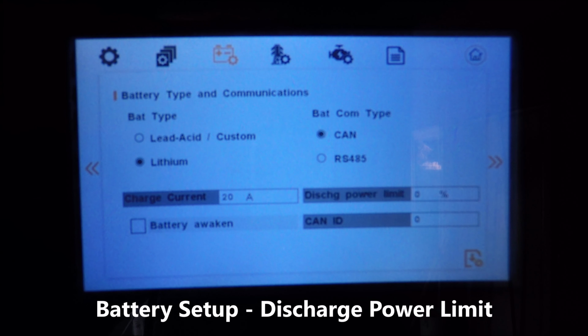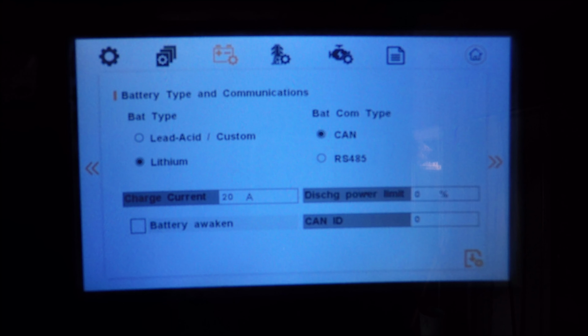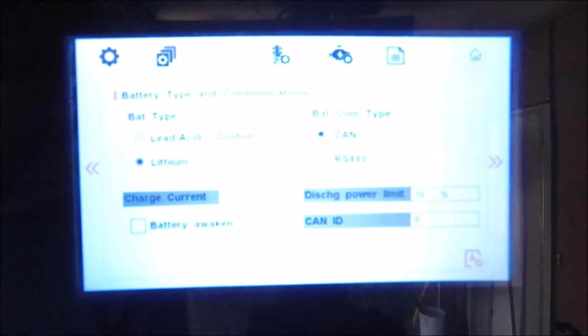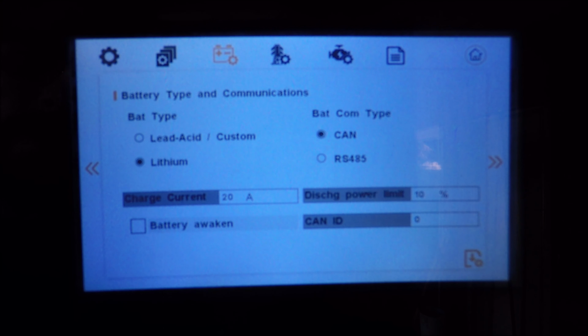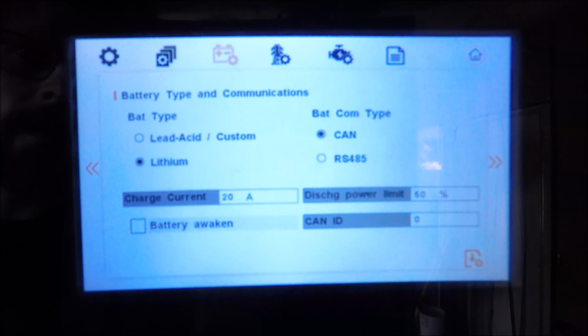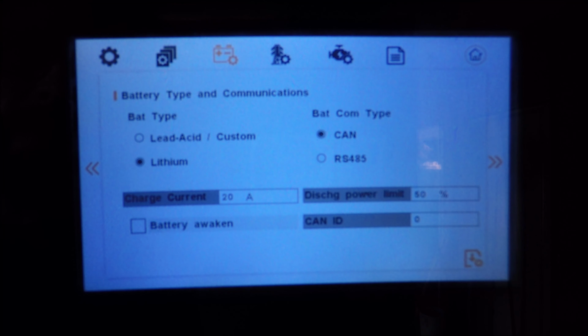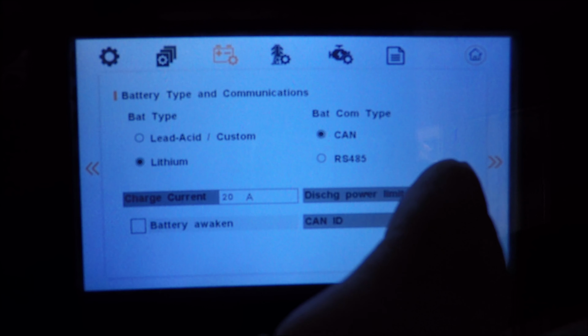For the discharge power limit, this is if you have the grid attached. If you set this, let's say, to 10%, this means that the inverter will draw 10% of its power from the batteries and 90% of its power from either solar or the grid. If you set this to 50%, then the inverter will pull 50% of battery power to the loads and then balance the rest of it between the grid and the solar. Now, if you do not have grid attached, it will simply balance the load between solar and battery. In my case, we're going to set this at 15%.